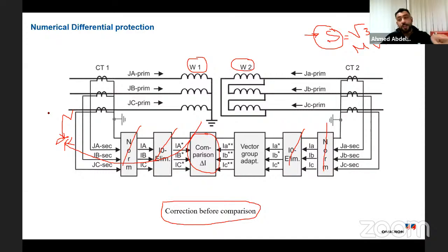If I didn't put this kind of comparison or correction into my consideration, the differential protection will trip in case of a single phase fault with an external fault, because the actual differential current will be divided by square root of 3. So if I compare the current from the secondary side with the current from the primary side, I will see a difference of 2 over square root of 3. This is significant enough to make the relay trip. So I need to tell my relay to do the correction of the I0 sequence elimination. This kind of correction happens only if I have a star grounded transformer. But in case I have a delta, it's useless.